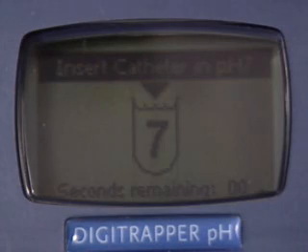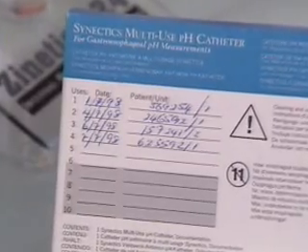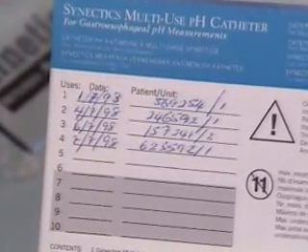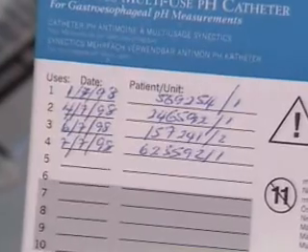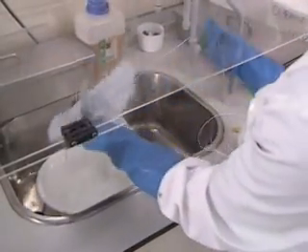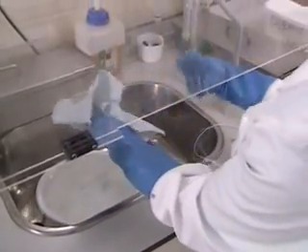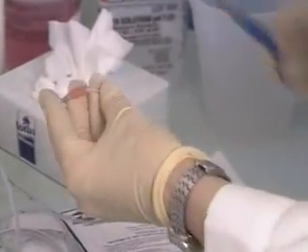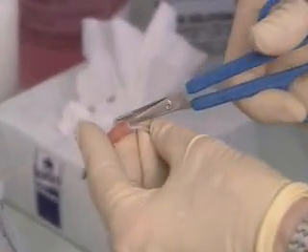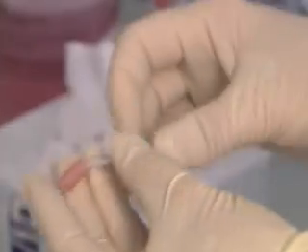The most common calibration problem is catheter failure. Multi-use catheters can only be used for a limited number of studies. The usage is mainly dependent upon the degree of acid exposure. Immediate and thorough cleaning will limit the buildup of organic debris over the pH sensor and maximize sensor life. For single-use catheters with internal reference electrodes, make sure you have removed the cover protecting the reference.